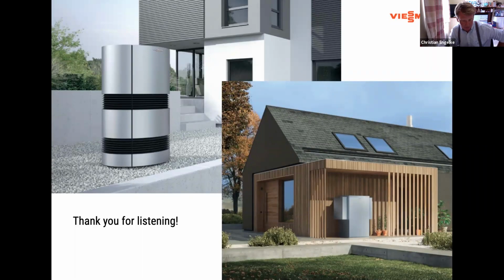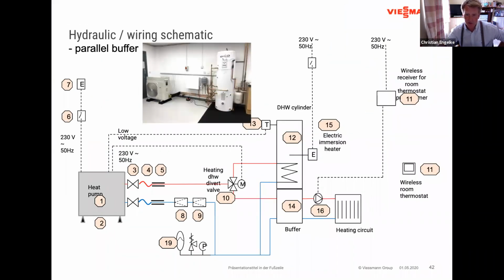And then within the property, if there's a buffer vessel fitted like I've shown you before, then from the buffer to your heating system, that could be your standard pipe sizes. So you can use your microbore systems, or any other pipe sizes you have, as I've shown here. I'll go back to this system here. If you have this type of installation, for example, the pipe sizes between the outdoor unit, let's assume the outdoor unit is close to the machine, and the buffer store, we say 28 millimeter, that's fine. From the buffer to your heating system, circulating the water to your radiators or underfloor system, that can be of your choice. And then the pump obviously will be calculated accordingly.